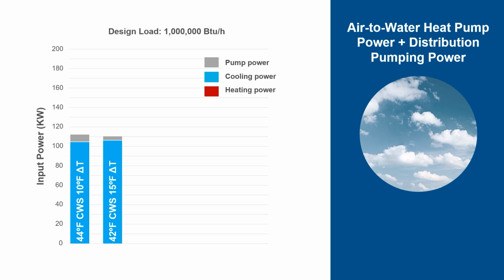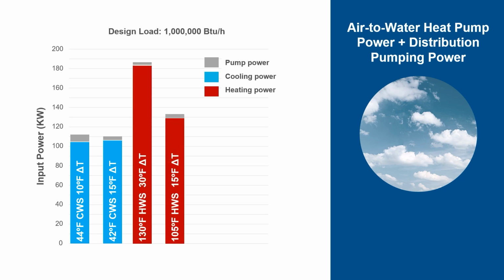This does require lowering the chilled water supply temperature to 42 degrees, but the additional compressor power is smaller than the pump power savings, resulting in overall savings. How about heating operation with a 1,000,000 BTU per hour heating load? The left red bar shows the air-to-water heat pump operating at a 10-degree ambient temperature and supplying 130-degree water to the fan coils. The right red bar shows a large power reduction when the heat pump supplies 105-degree water.